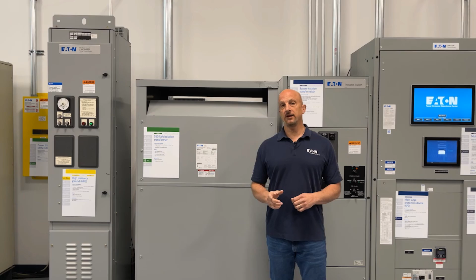So this next transformer is a little bit unique. We call it an isolation transformer, and what does that mean? That means the voltage on the input and output are the same, so we're just using it to reestablish a ground system through the delta Y and the Y connection on the secondary. This one happens to be 460 in, 460 out, 550 kVA. It's also connected, in this case not solidly grounded, but to our high resistance ground system, which allows us to have one free ground fault, and you might use that on an industrial situation, for example.